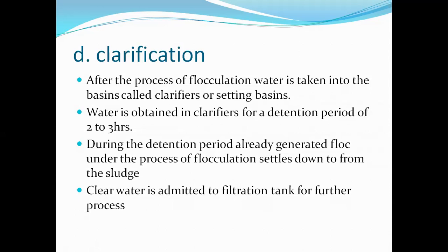In clarification or sedimentation, after flocculation, water is taken into basins called clarifiers or settling basins, and water is retained in clarifiers for the detention period of 2 to 3 hours. That is, water is going to settle in the clarification tanks for 2 to 3 hours. During this detention period, the already generated floc under the process of flocculation settles down to form the sludge.